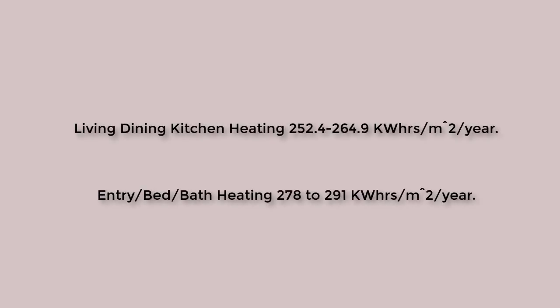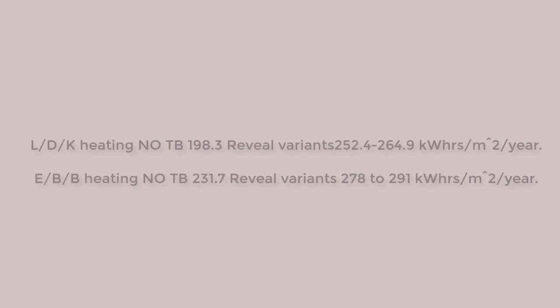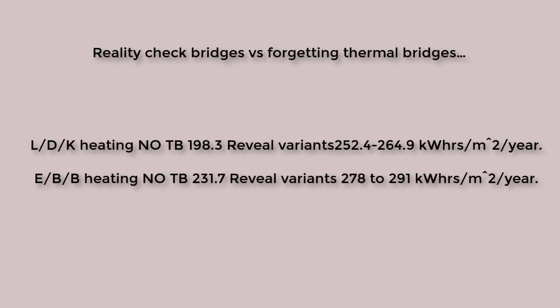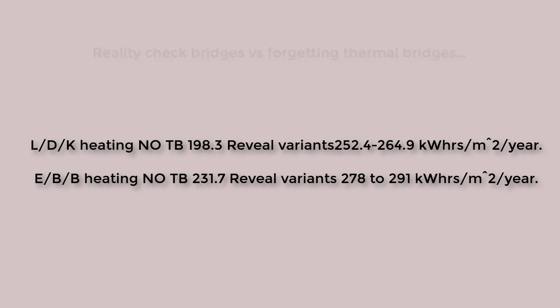With normalized heating on an annual basis, for the living spaces it increases by 12.5 kWh per square meter per year, and for the non-living spaces by 13 kWh per square meter per year. Are those big numbers? Well, if we were to remove the definition of thermal bridges from the model, that has more impact — but consider that those psi values are the conservative K1 table values used in the UK for those who can't be bothered to supply a calculated value.